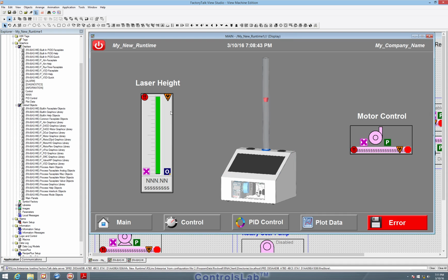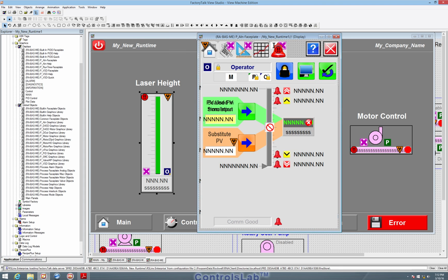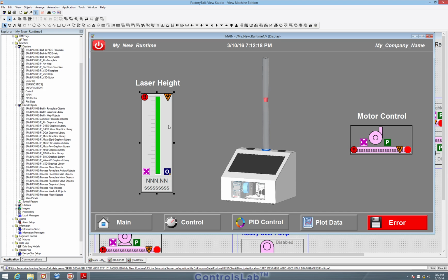So with that set, now when we click on this control, the global object will automatically open the associated P_analog_in faceplate. So when they click on this global object, this faceplate will come up. And all of these controls are associated with this faceplate. Keep in mind we had this pop up 300 pixels over, so this should still be visible and the faceplate will show up in this area of the screen covering our image, but that's okay because we can close this faceplate when we're done changing things. So now that control is linked to the programming and is ready for live interaction with the user. This control is completely set up and done.